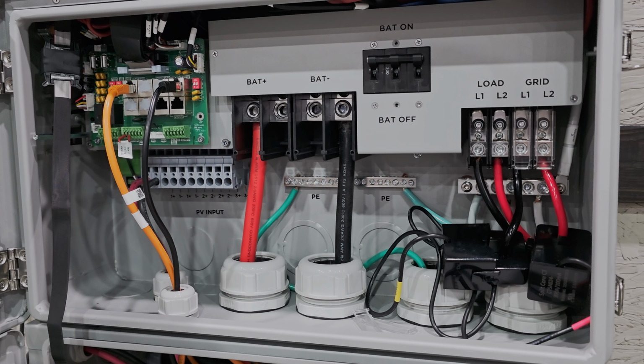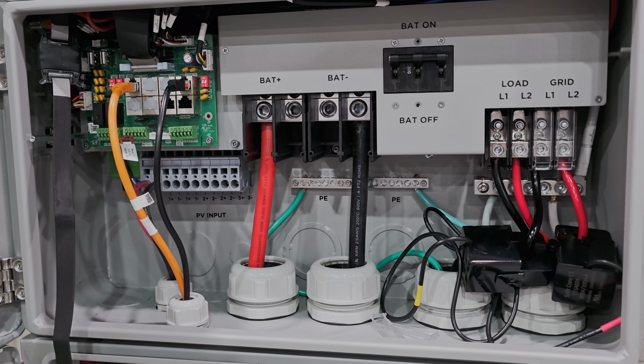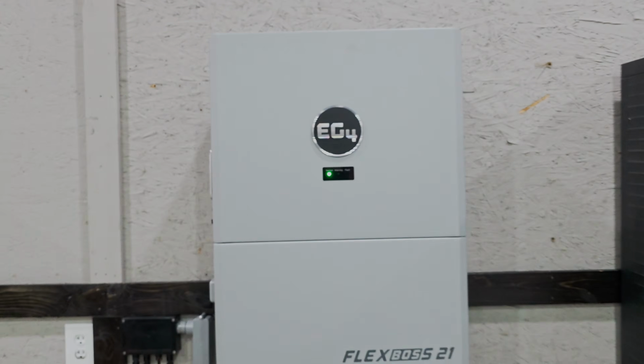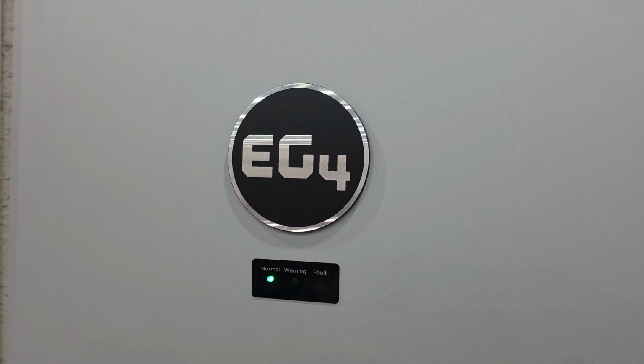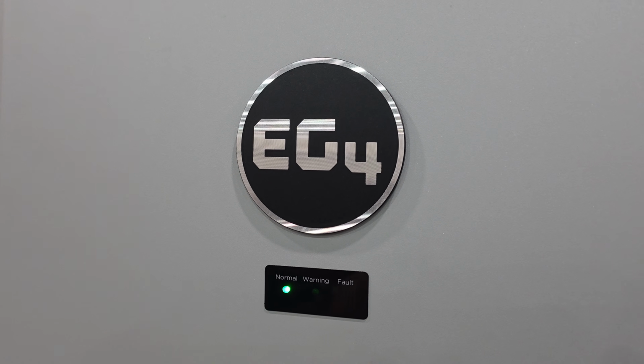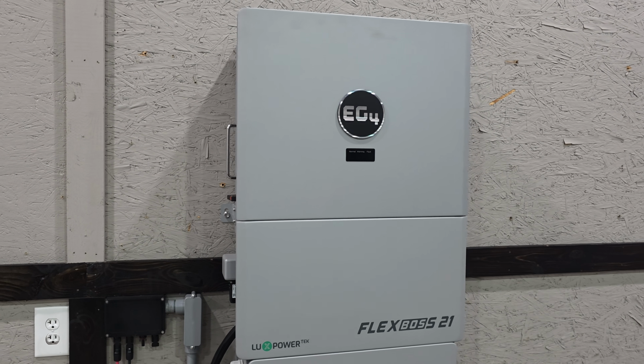Now, the important design numbers are not just the maximum voltage. The MPPT operating range is between 120 volts to 440 volts. The full power range is between 250 volts to 440 volts. And the startup voltage is 200 volts. So when you're designing strings, you need to size everything properly. You just don't throw panels at it and hope for the best. But the point is, EG4 gives you a pretty flexible solar input platform.